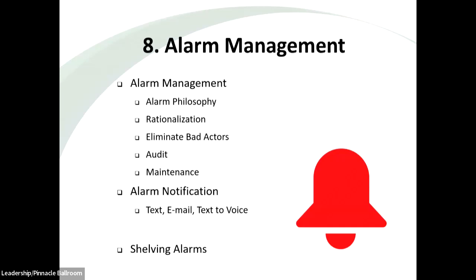An audit is a necessary step in the alarm management process, and then the maintenance of that process. Current SCADA systems should have the functionality to text, email, text-to-voice, and have all of those things available as needed for operations. The last feature I wanted to mention is shelving alarms. Shelving alarms is kind of like putting a site in maintenance mode, so that no alarms are actually broadcast. But the beauty of shelving alarms is that it automatically expires and re-enables the alarms for that particular site, so you don't have to remember to turn the maintenance mode off, which I think we've all done at some point.